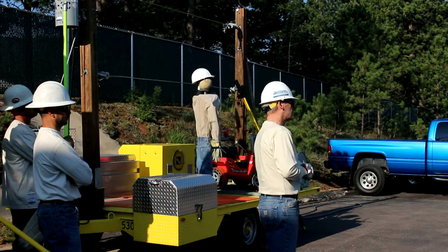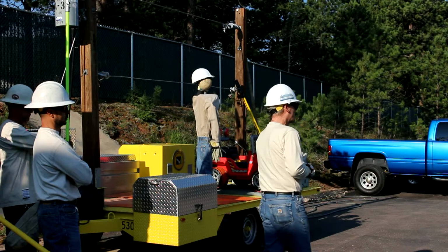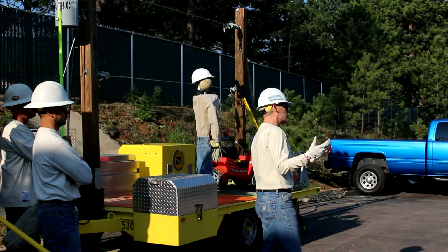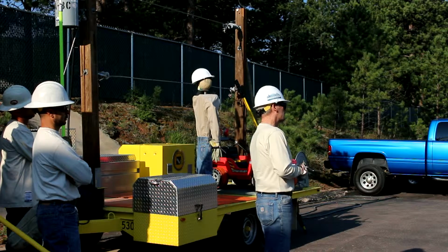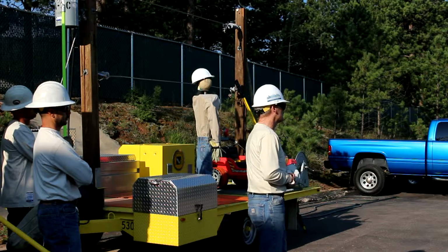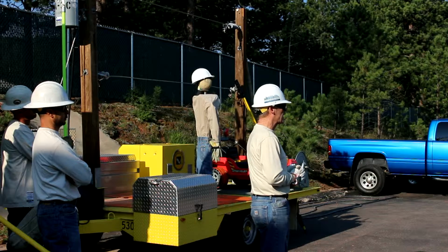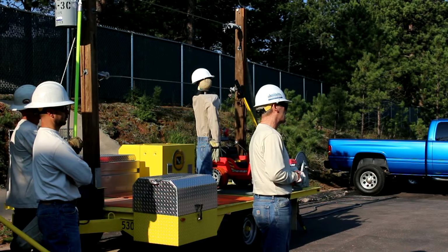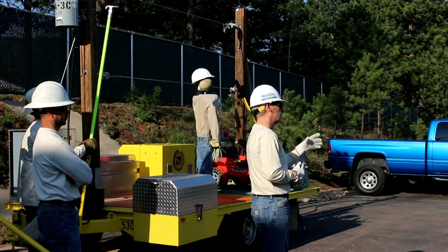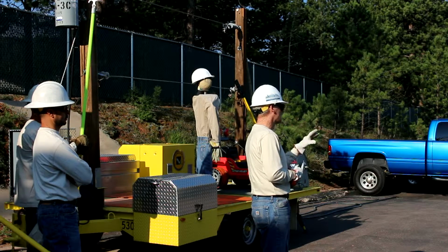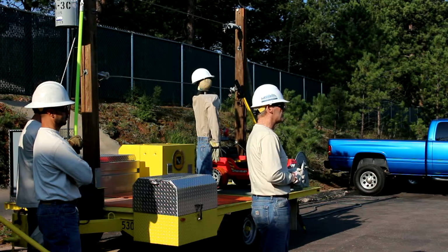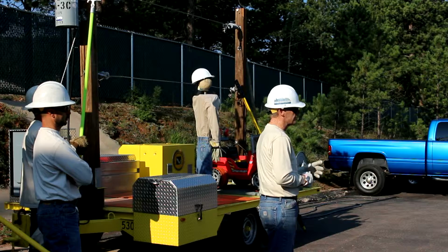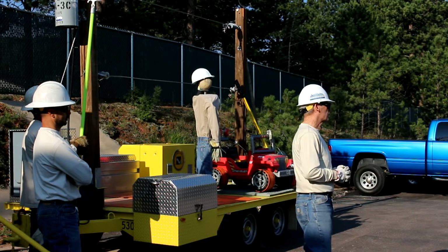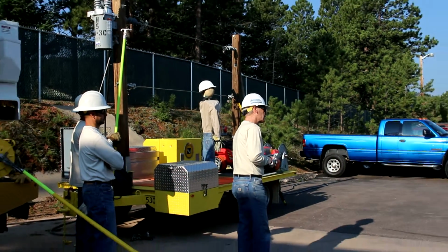Even with you guys working on trees, the work could be done in the neutral, but if the bond is open, that could be the path to ground. So even removing the tree from the neutral, you could be the path to ground. You have to be very cautious about how you work it. You guys have pretty stringent regulations for working trees in or near energized lines, and that's good - we know what your safety practices are. We're just helping you appreciate that.